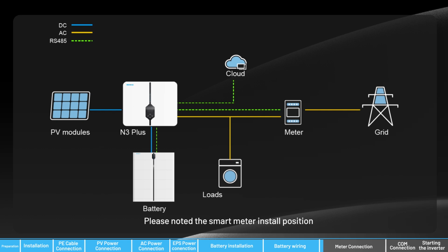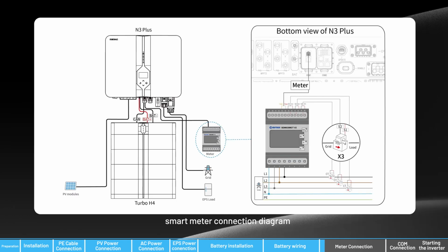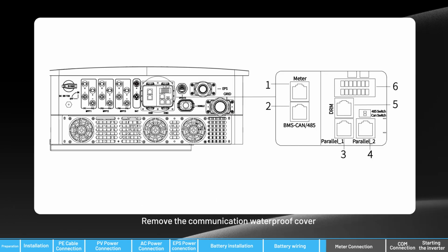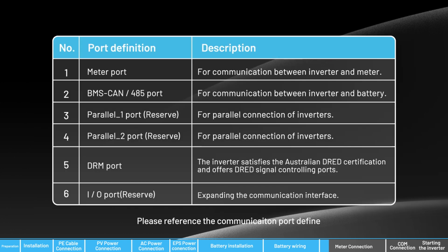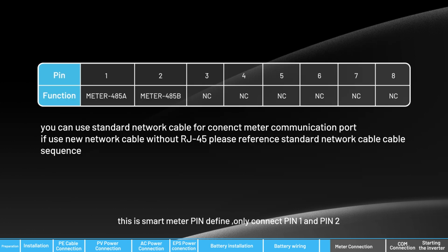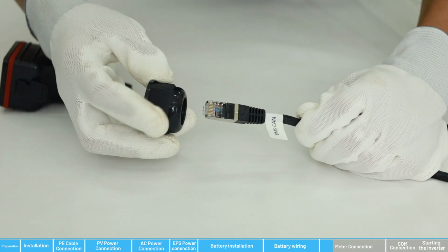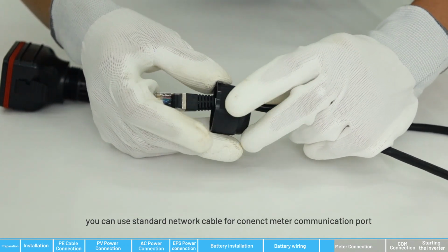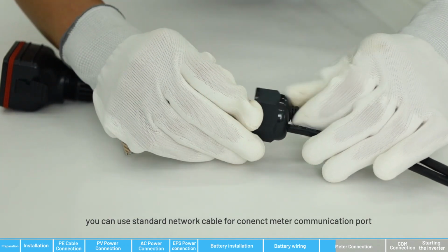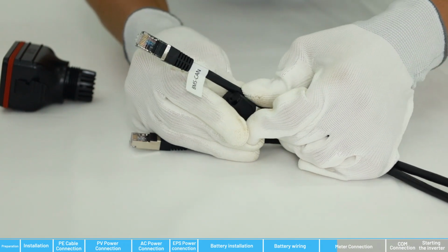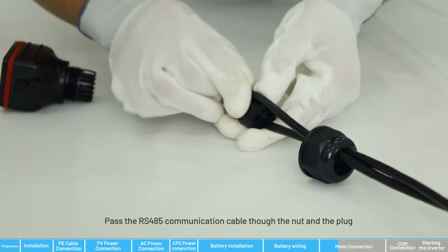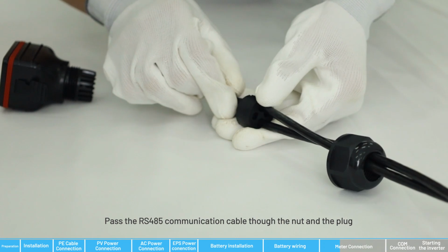Please note the smart meter install position and smart meter connection diagram. Remove the communication waterproof cover. Please reference the communication port definition. This is smart meter pin definition. Only connect pin 1 and pin 2. You can use standard network cable to connect meter communication port. Pass the RS485 communication cable through the nut and the plug.